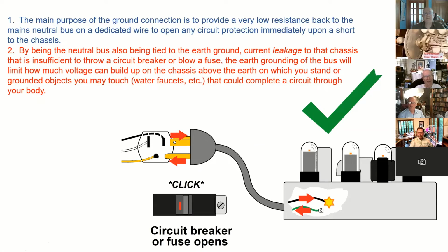Okay. Again, the main purpose of the ground connection is... my internet connection is unstable. Hopefully I'm still on. The main purpose of the ground connection, again, is to provide a very low resistance path back to the mains neutral bus on a dedicated wire, to open any circuit protection immediately upon a short to the chassis. With the neutral bus also being tied to earth ground, for leakage current to the chassis that is insufficient to throw a circuit breaker or blow a fuse, the earth grounding of the bus will limit how much voltage can build up on the chassis above the earth on which you stand, or grounded objects you may touch, water faucets, etc. Say there's just 100 milliamps. We'll just say that because that's the standard at which it's fatal.